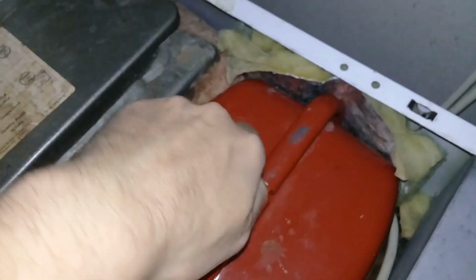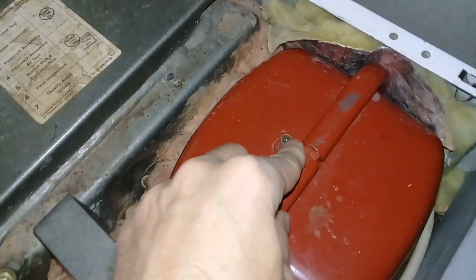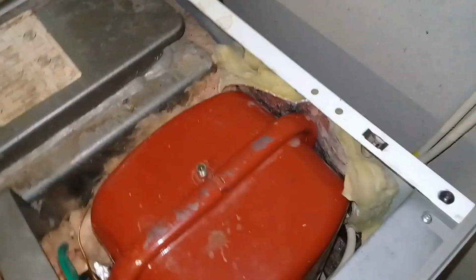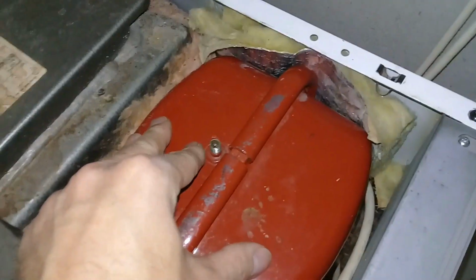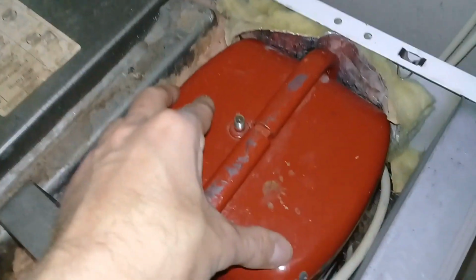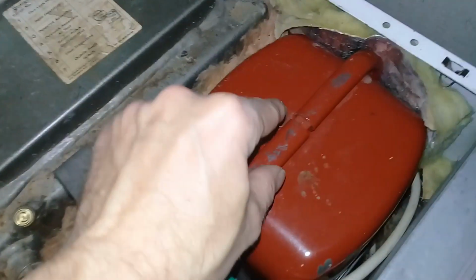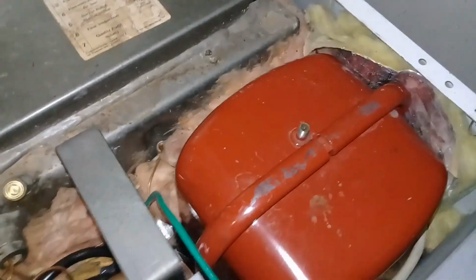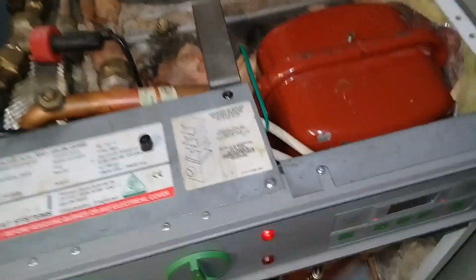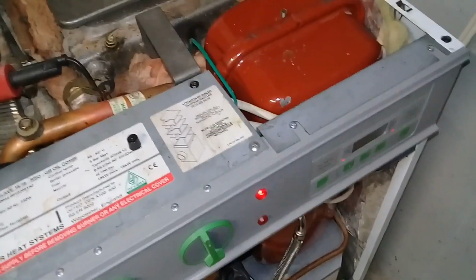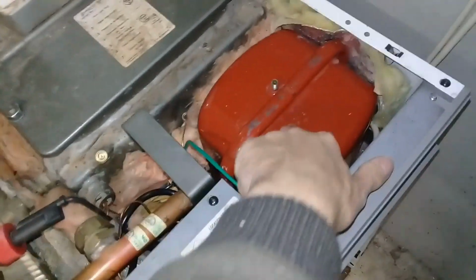Check this, when you take this off, I'm not going to do it because I've still got to change this one. But when you press the Schrader valve in, if water comes out, this is knackered. It means that the water's breached the balloon, as it were. 'Cause this is just like a football in there of air that allows the boiler pressure to go into here. So when these go, pressing the valve, water should come out. But on this one, it didn't. Also, what you'll also get, if this has failed, is no room for expansion.